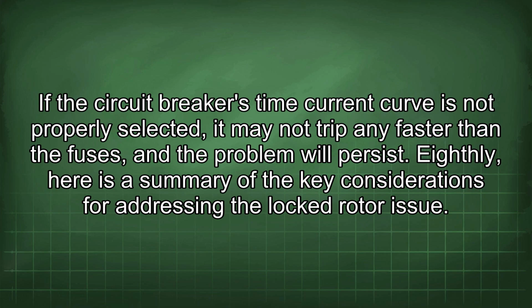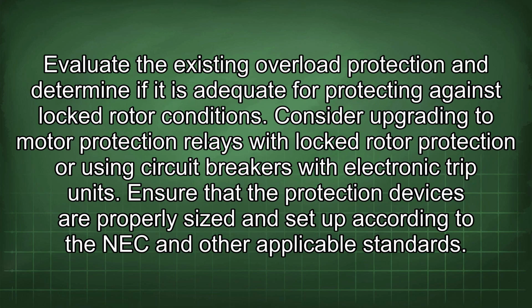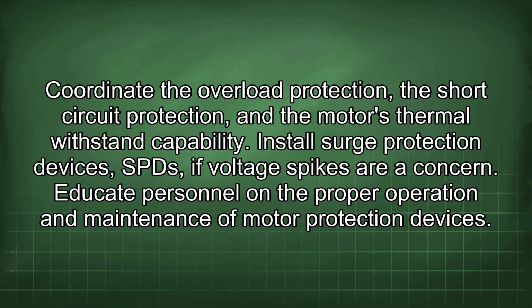Eighthly, here is a summary of the key considerations for addressing the locked rotor issue. Evaluate the existing overload protection and determine if it is adequate for protecting against locked rotor conditions. Consider upgrading to motor protection relays with locked rotor protection or using circuit breakers with electronic trip units. Ensure that the protection devices are properly sized and set up according to the NEC and other applicable standards. Coordinate the overload protection, the short circuit protection, and the motor's thermal withstand capability. Install surge protection devices, SPDs, if voltage spikes are a concern. Educate personnel on the proper operation and maintenance of motor protection devices.